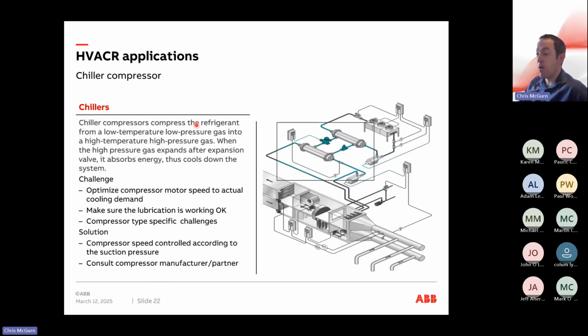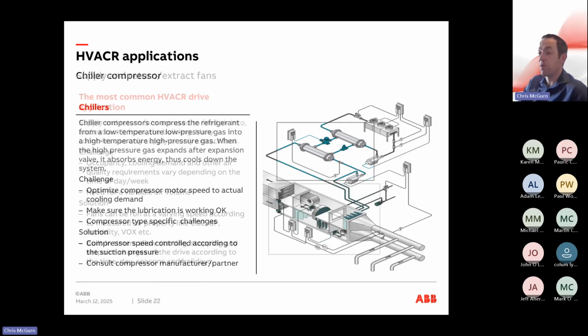Chillers are another form where VSDs can help in the application itself. So the compressor motor needs to be optimized to meet the actual cooling demand. It needs to make sure that lubrication is working okay, and there can be different challenges depending on what the specific compressor type is. So how VSDs can help: the compressor speed is controlled according to the suction pressure itself. And it's just about maintaining the correct speed and ensuring you're running at the peak efficiency for what the system itself requires.